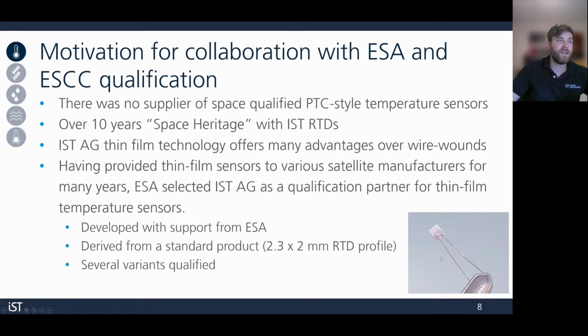So this image we have here is the profile that you'll see for all of these sensors. They all have the same form factor. The only difference is the temperature rating on some or the nominal resistance, but the chips overall look identical, and they're based on an existing chip size that's very popular for us, which is this 2.3 long by 2 wide chip size.